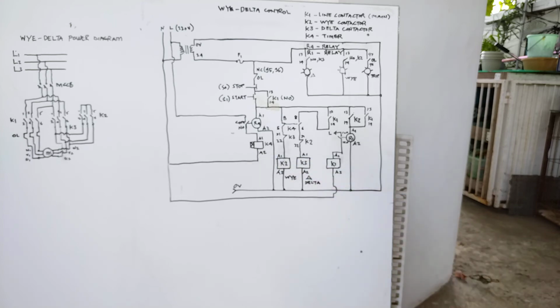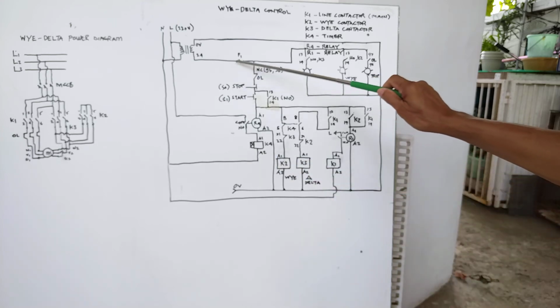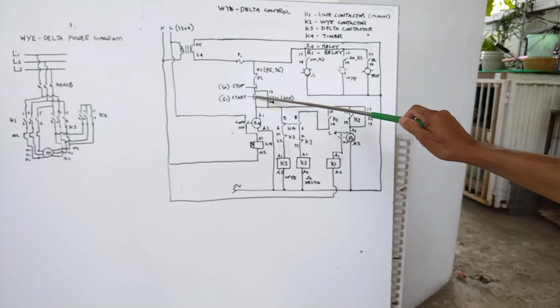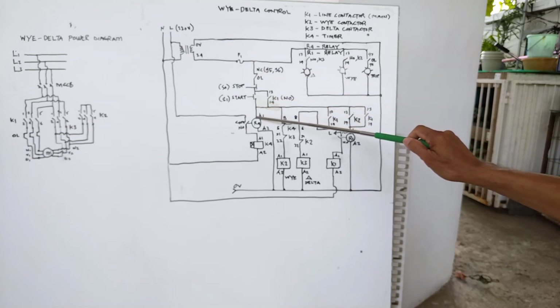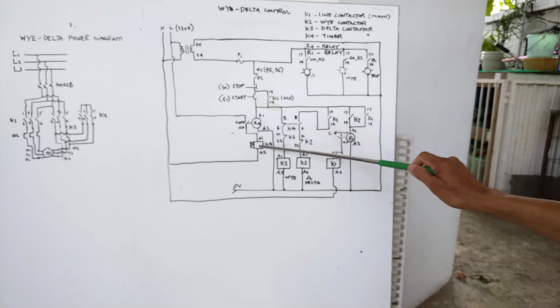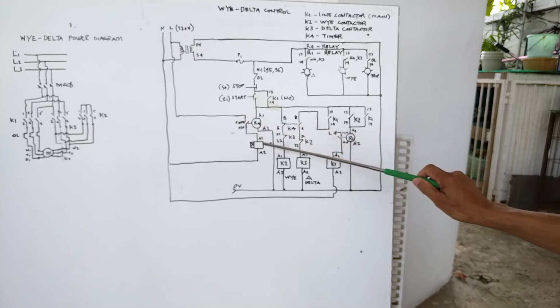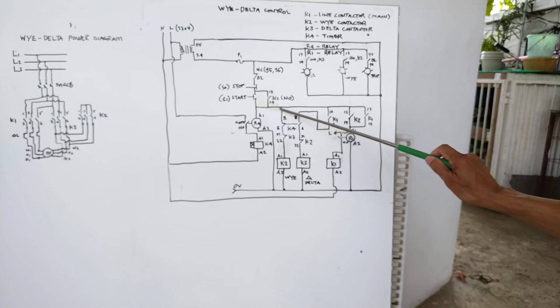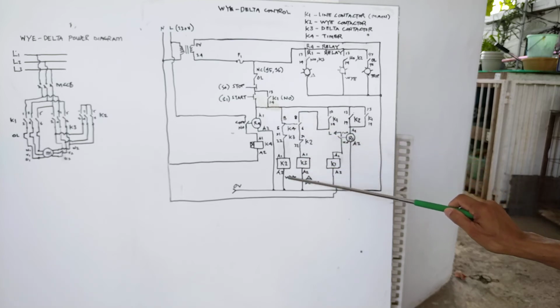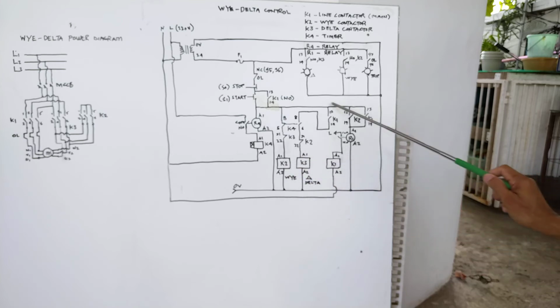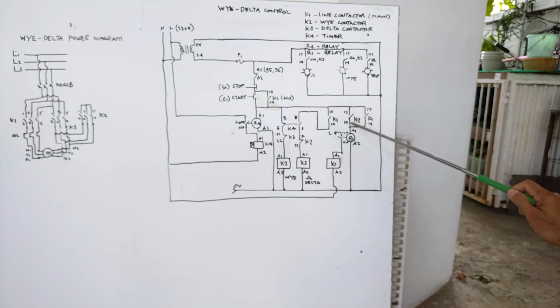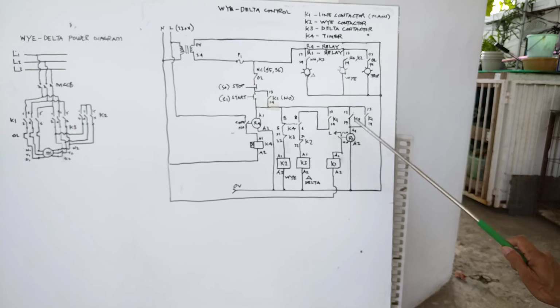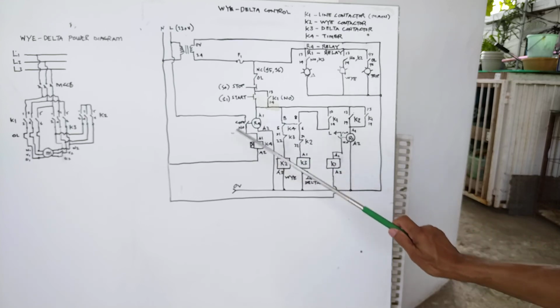So let's trace it again. 24 volts will come here, then we push, then 24 volts will come here. Then this one will be energized, and 220 will come here, energizing our timer. At the same time, this Y delta is energized. Then, since this is energized, this one will close, so 24 volts can also come here, energizing our line contactor. So the line contactor, Y, and timer are energized.